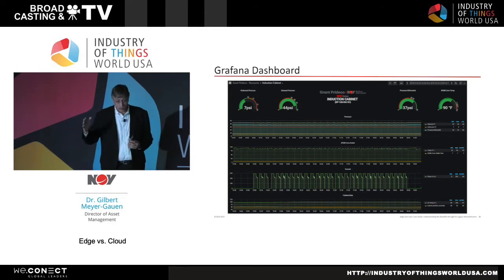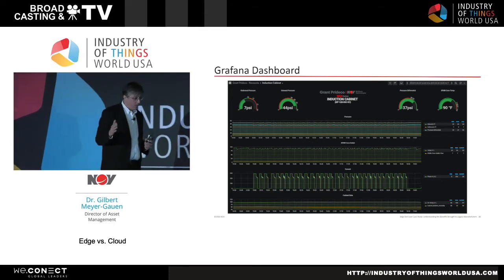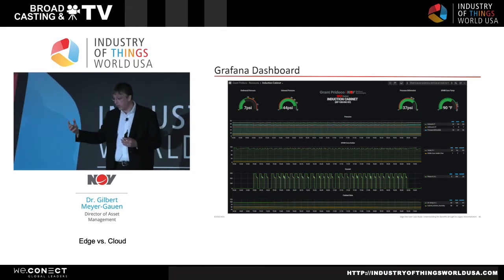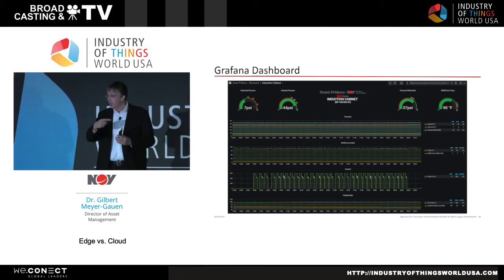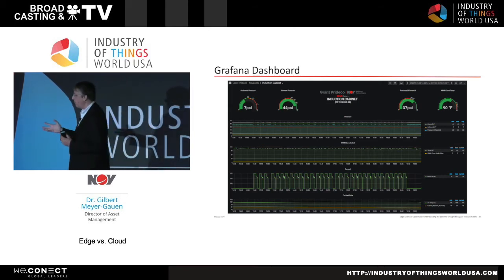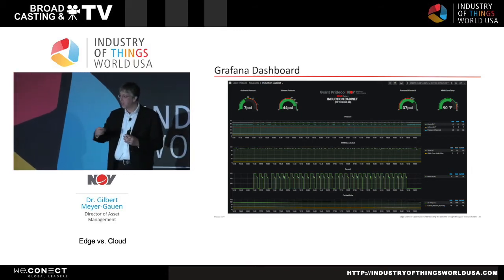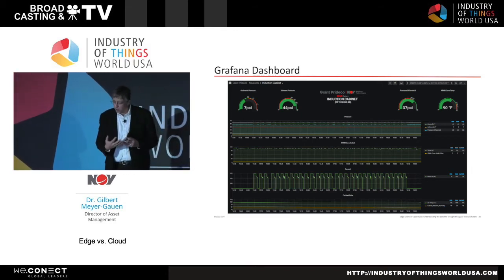Case in point, this is a real life example from our facility, from a slightly different equipment. I think it was a welder that is oil-cooled, and it has water pipes going through the oil bin to cool down the oil. So for whatever reason, that water pipe had leaks in it. And now the water was getting into the oil.